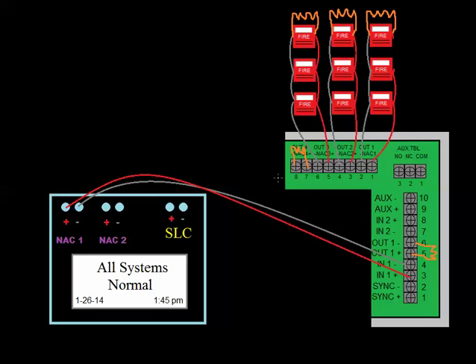It's configured for a door holder, which means in a normal state, when the panel's clear, you're going to have a constant 24 volts coming off of those terminals. And when the panel goes into alarm, it's going to drop out.